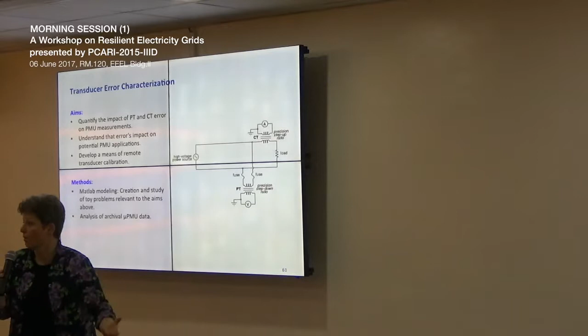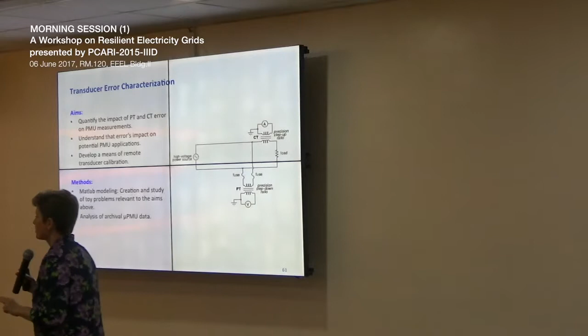So if the transducer has 0.3% error, my measurement is going to have 0.3% error, which is way worse than the actual micro PMU. The good news is that error is stable over time, so we ought to be able to do some clever regression and fancy math that my PhD students know how to do, and recover that error and get it out. In fact, we can try algorithms that take differences before and after, so the error drops out.